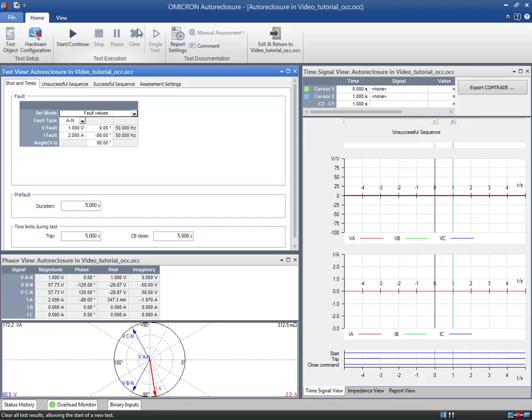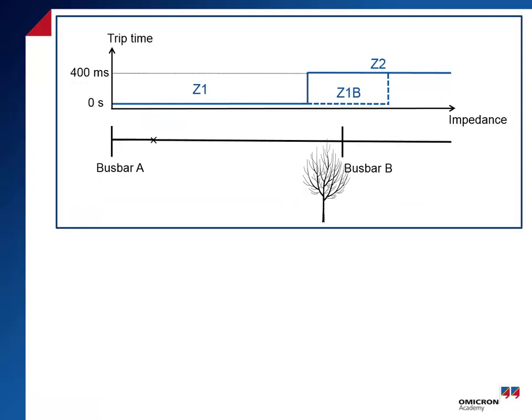In this example, we will test an automatic reclosing with only one reclosure cycle, but remember that you can test up to 15 cycles in the test module. According to the relay under test, the extended zone Z1B is enabled before the first auto reclosure. This means that the relay trips instantaneously for faults up to 120% of the line impedance.